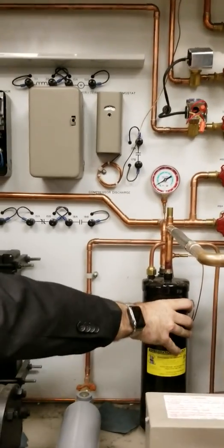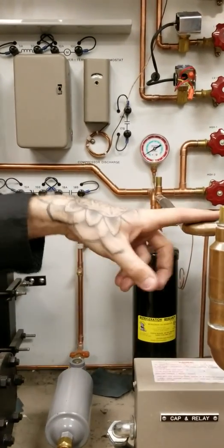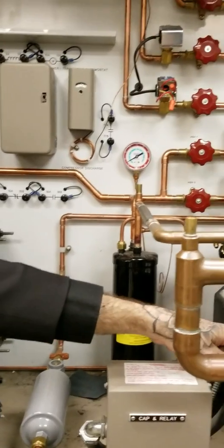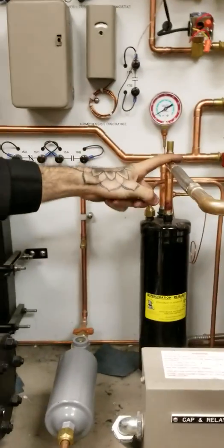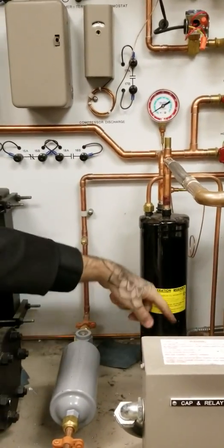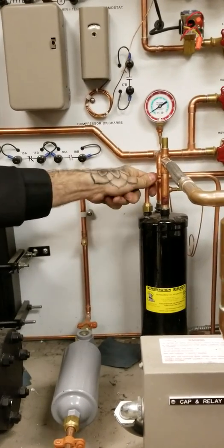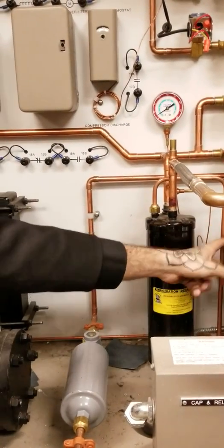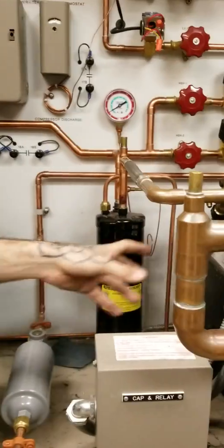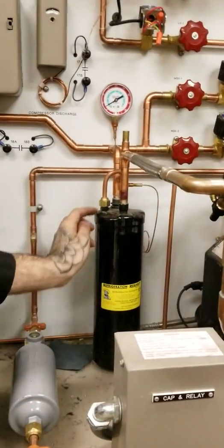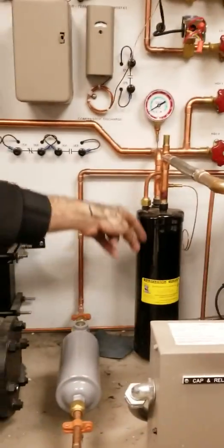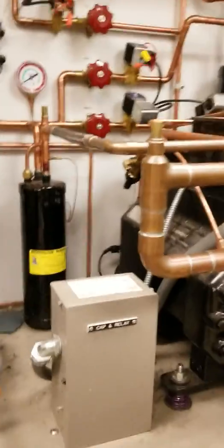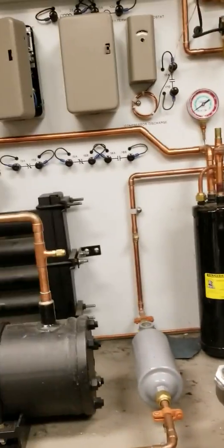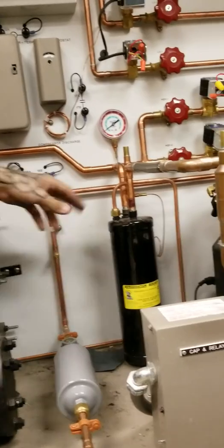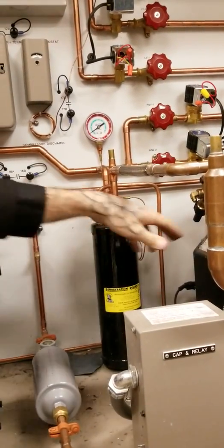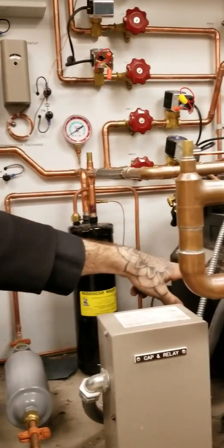Right here is an oil separator. So the design on this is your hot gas comes in, this thing's loaded with oil, it's going to be shooting some out. And if that oil builds up in here, you have this right here that's connected to your suction line. If you follow it through, it taps into the suction side of the compressor and has a straw that goes all the way down, and that's going to suck the oil back into the compressor before it shoots the oil. I mean, you're going to get some oil through the system, but the majority of it is going to make it back to your compressor so you don't overheat.